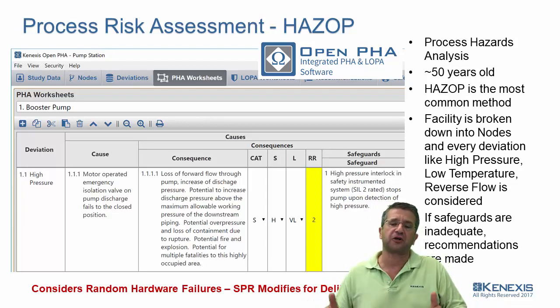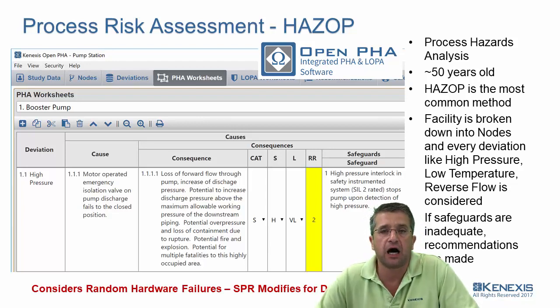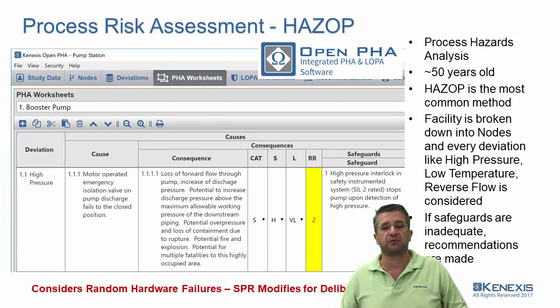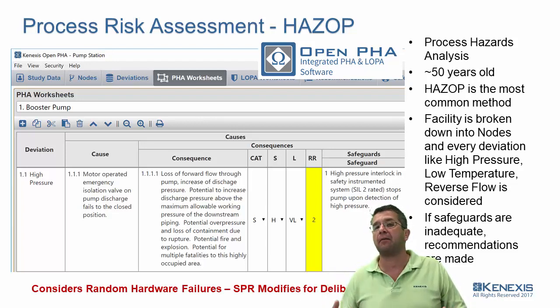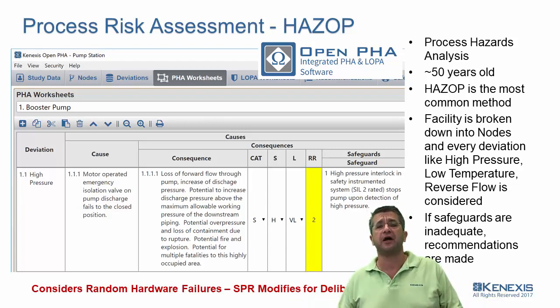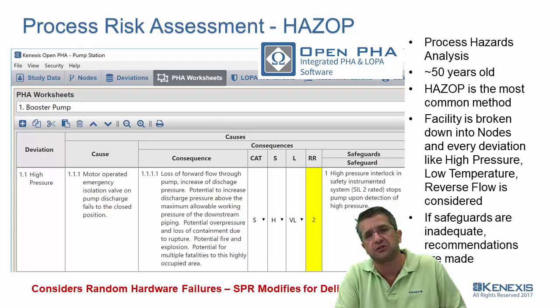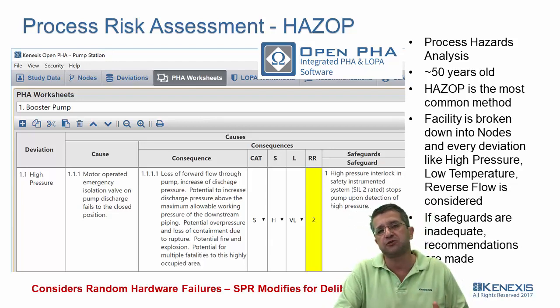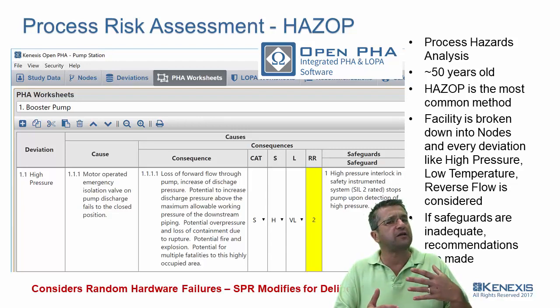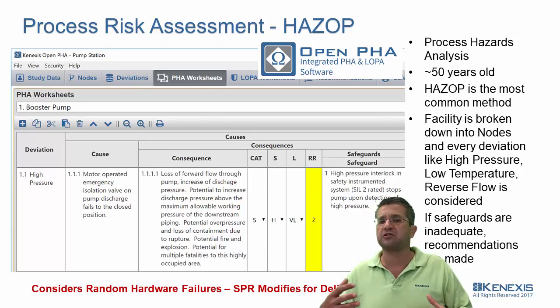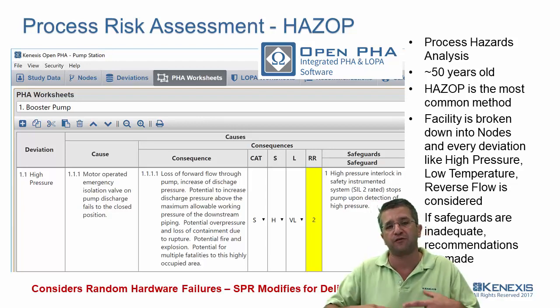Let's look at what is traditionally done to make sure a process plant is designed safely — the process hazards analysis process. We've been doing PHAs for more than 50 years. HAZOP, the Hazard and Operability Study, is the most common method. When you do a HAZOP, you take your entire facility, break it down into nodes, and for each node you look at every deviation like high pressure, low pressure, high flow, no flow, low flow, and reverse flow. For each deviation you determine what could cause it, what the consequences are, and what safeguards are available to prevent it from turning into the consequence.